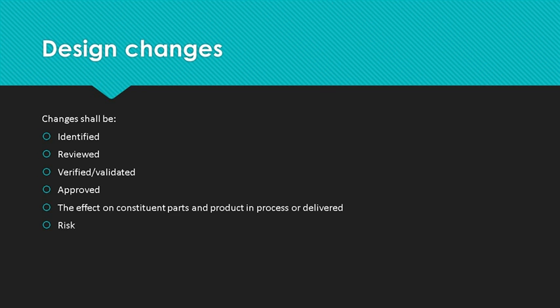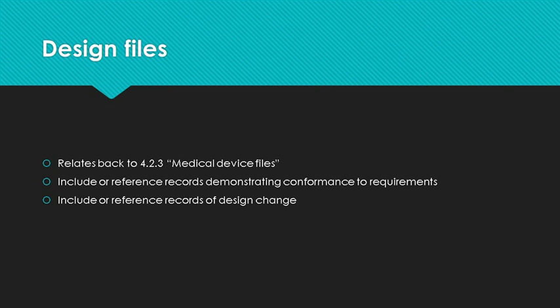So as defined in section 4.2.3, a medical device file shall be maintained for each medical device family and include or reference records to demonstrate conformity to requirements and records of design change. So the output of this design needs to be part of this medical device file. You don't need to have all of the design files and the plan and the change in the medical device file. Those can be held as part of the design files, but there should be a reference to the conformity to requirements and to any recorded design changes.